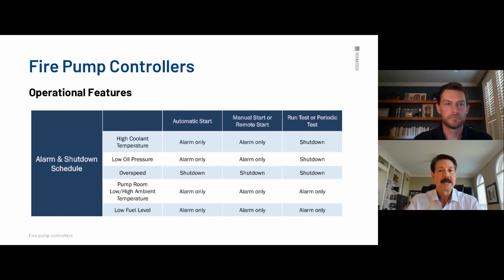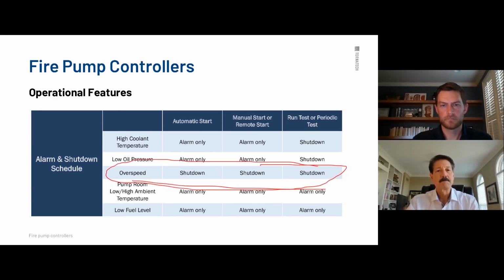But if you do the run test, because it knows it's a test, any of those items will cause, well, typically the main ones, high coolant, low oil pressure, will cause it to shut down. When you get into low or high ambient pump temperature, it's alarm only, or low fuel level, it's alarm only. The one item that will shut down regardless if it's a fire or not is overspeed.